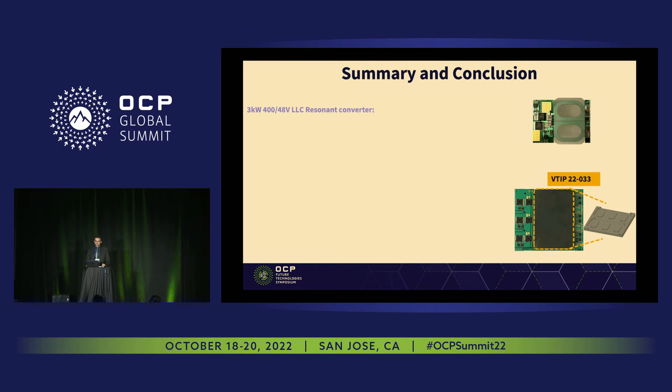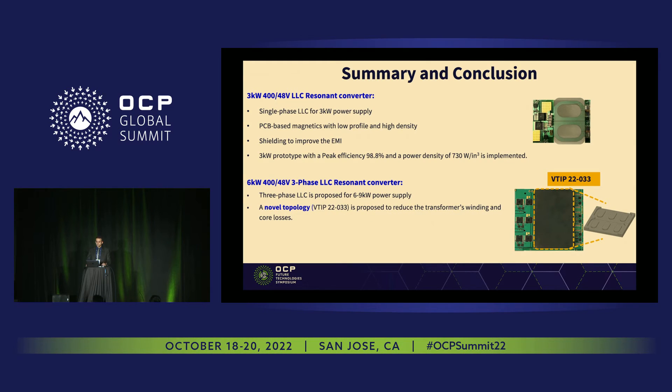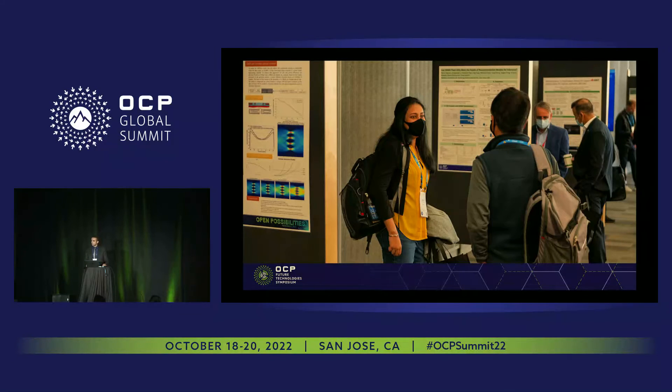In summary and conclusion, we have two solutions. The first is a 3 kilowatt, 400 to 48 volt single-phase LLC converter with PCB-based magnetics and shielding for EMI — achieving 98.8% peak efficiency and 730 watts per cubic inch power density. Our next generation is a three-phase 6 kilowatt, 400 to 48 volt design with a novel topology to reduce transformer winding and core losses, and novel magnetic integration for symmetry between the three phases with no current sharing issues, better core loss distribution, and improved winding loss — achieving 99.1% efficiency and more than 1,000 watts per cubic inch power density.